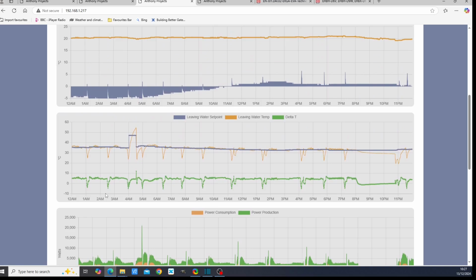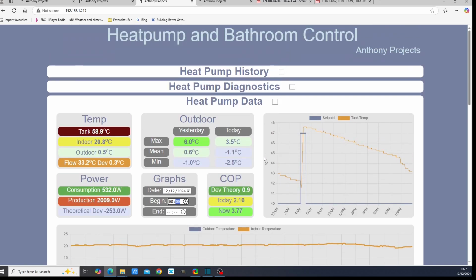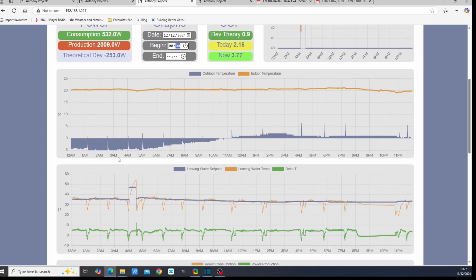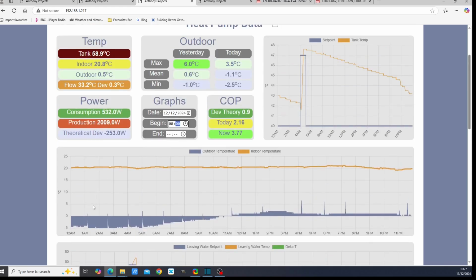And you can see throughout the whole day, even when the temperature is above freezing point, you'll still get a defrost cycle because the temperature of your coils is lower, they're below freezing point. So that is a basic anatomy of the coldest day since I have been in operation. And as you can see, we've had no trouble maintaining good temperature inside the house.